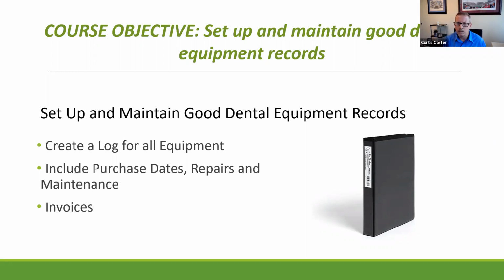So, a log, a 3-ring binder like we've got pictured here, something that's prominent in the office and labeled so everyone knows where it is and what's in it is going to be key. Why is it important? It's going to help keep your existing equipment running reliably. This whole program is really about uptime, reducing downtime, which is costly to your bottom line and to your practice. It's going to help extend the life of the equipment because you can monitor your maintenance and make sure that it's getting done correctly. The other thing, and I don't think a lot of people think about this, but if you are maintaining good equipment records, it's going to help you plan for replacement equipment purchases.